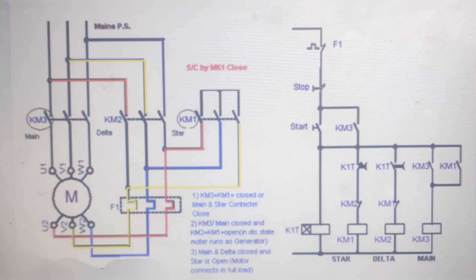The delta connection occurs in this power circuit. Many people have confusion while connecting the motor terminals, so look at this diagram and follow the same way. In star contactor, make a star point, do the short in star contactor input, and in output you have to connect U2, V2, W2 terminals of the motor.